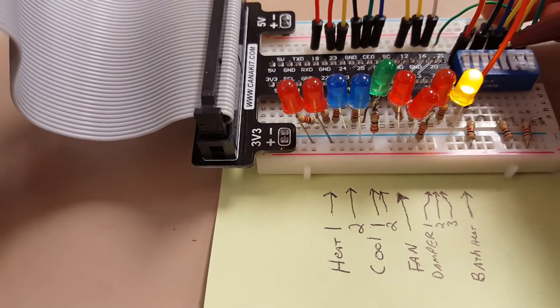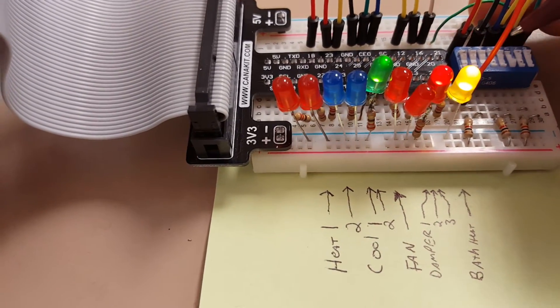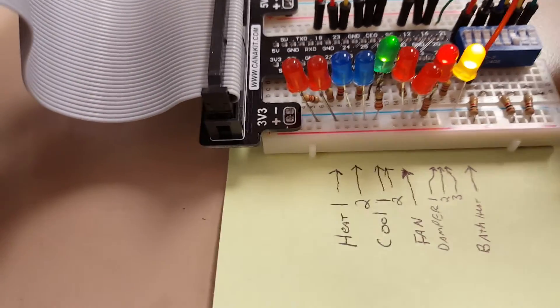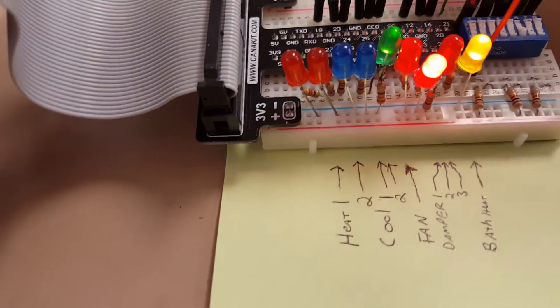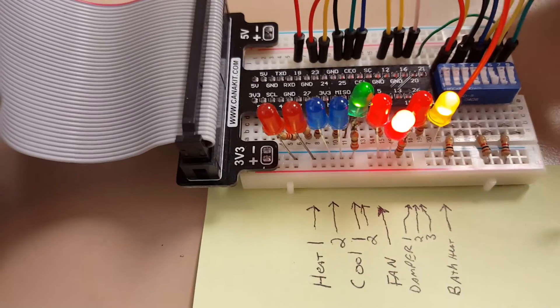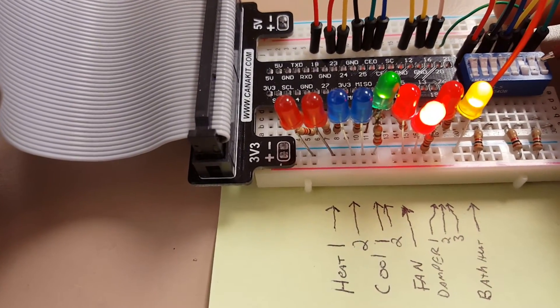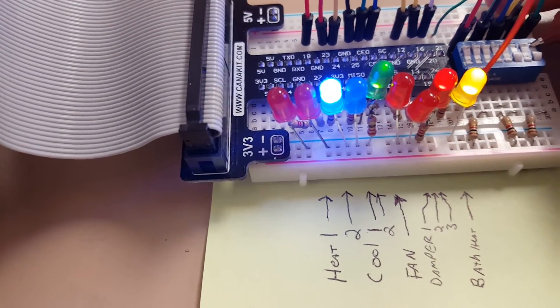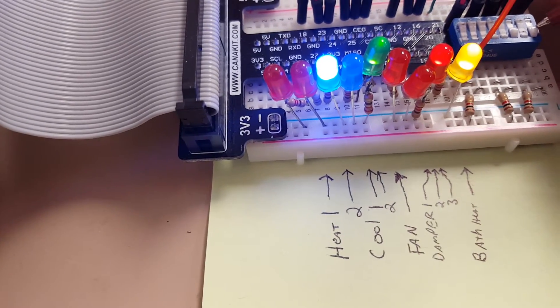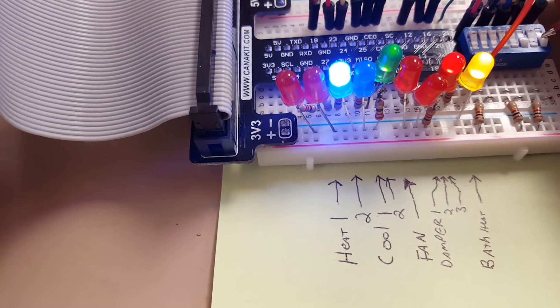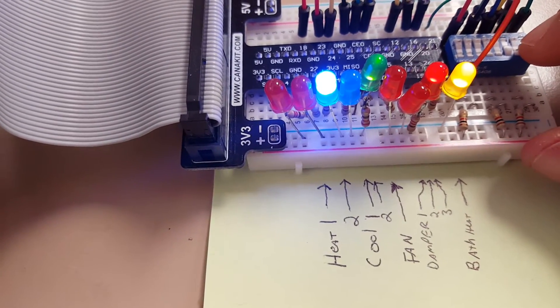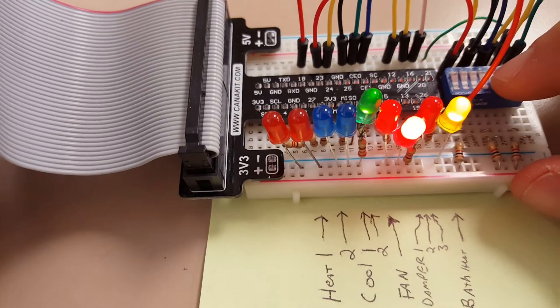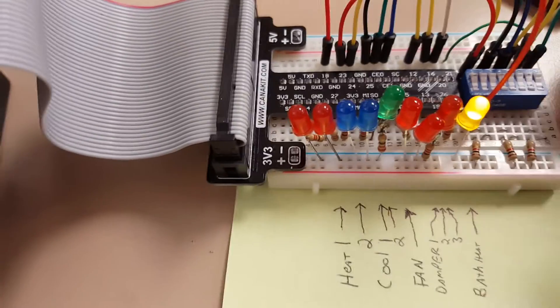If we're running just fan-only mode, let's say middle zone, here we go. Middle zone is running fan only. If there's a call for cooling, that's going to shut off that zone damper and open the one that needs cooling. That way an area that wants ventilation is only going to get ventilation and not heating or cooling, so it's a little bit, try to be a little bit intelligent with it.